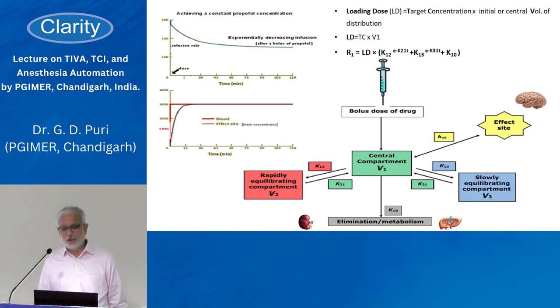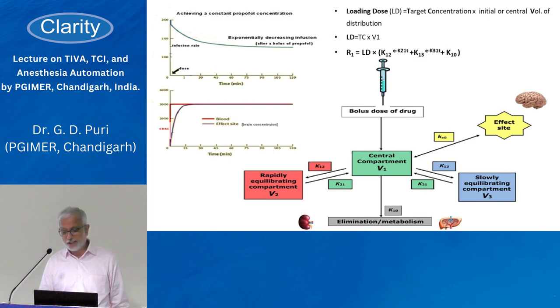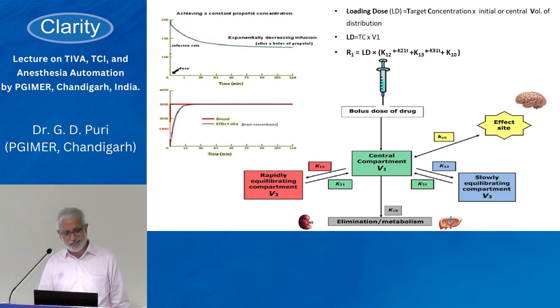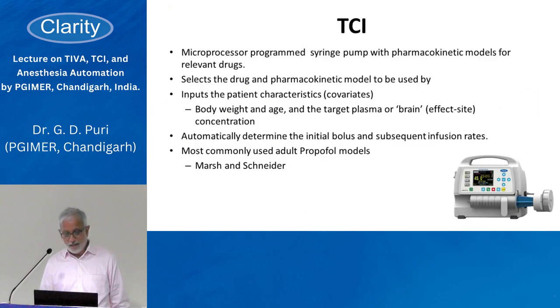Simply define the loading dose based on target concentration and initial volume of distribution, then use a decreasing rate of infusion dependent on the fixed elimination constant K10 and the variable distribution constants into the rapidly and slowly equilibrating compartments. Once you inject, blood concentration is achieved quickly but the effect-site concentration takes time. The amount of drug needed to maintain concentration keeps decreasing over time — a decreasing rate of infusion. This algorithm is programmed into target-controlled infusion (TCI) pumps, which are very costly.